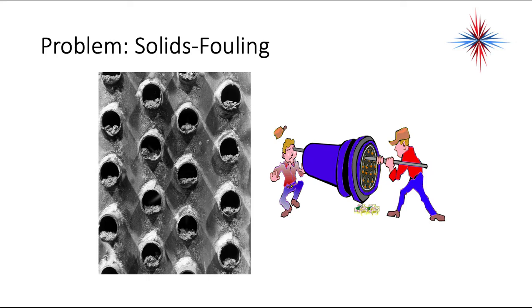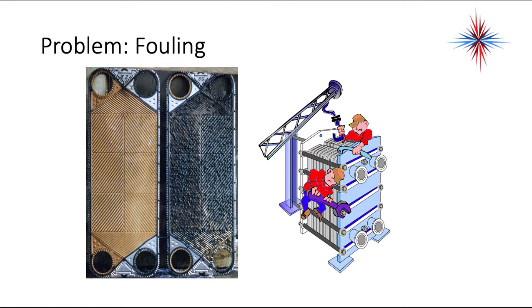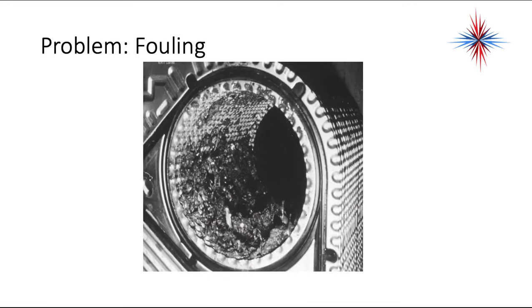One of the problems is that the solids cause fouling in the chiller barrels. This is the side of a chiller barrel with the covers off — you see all the little tubes and the buildup at the bottom of the tubes. Every bit of buildup reduces water flow. Here's another example of a plate chiller taken apart — you can see the clean one on the left and the fouled one on the right. That's all contamination that came in through the cooling tower loop.